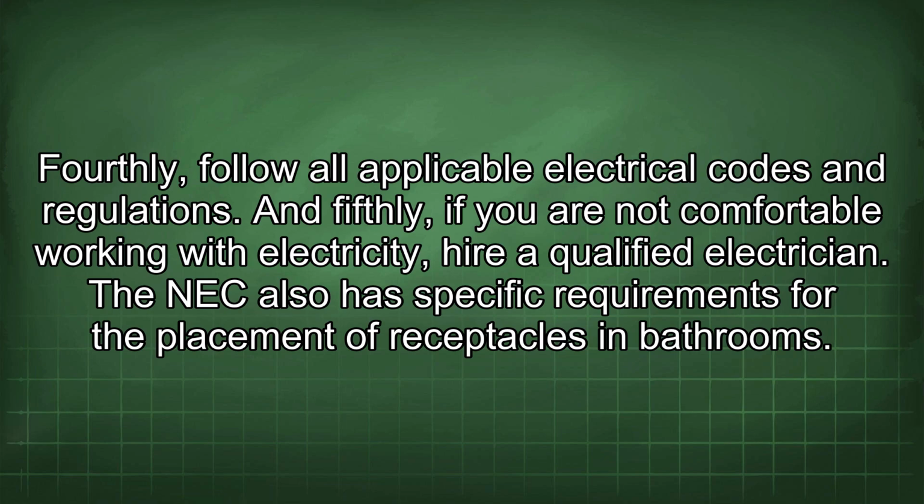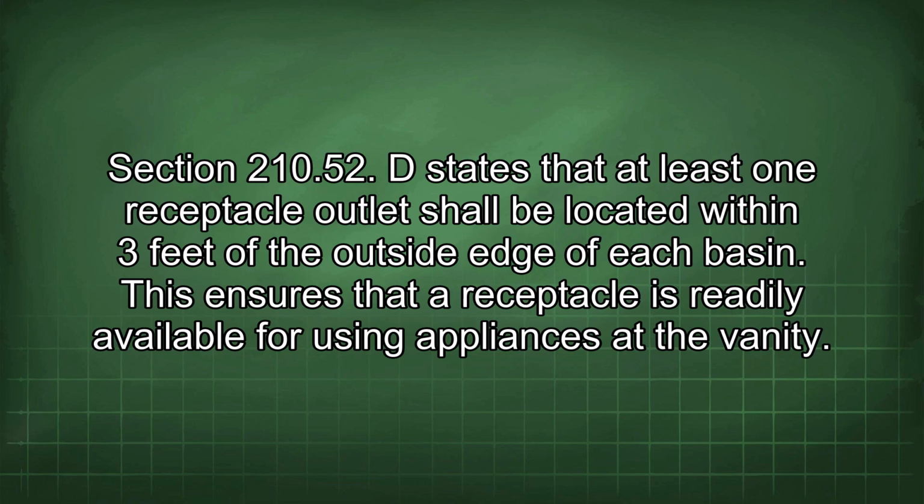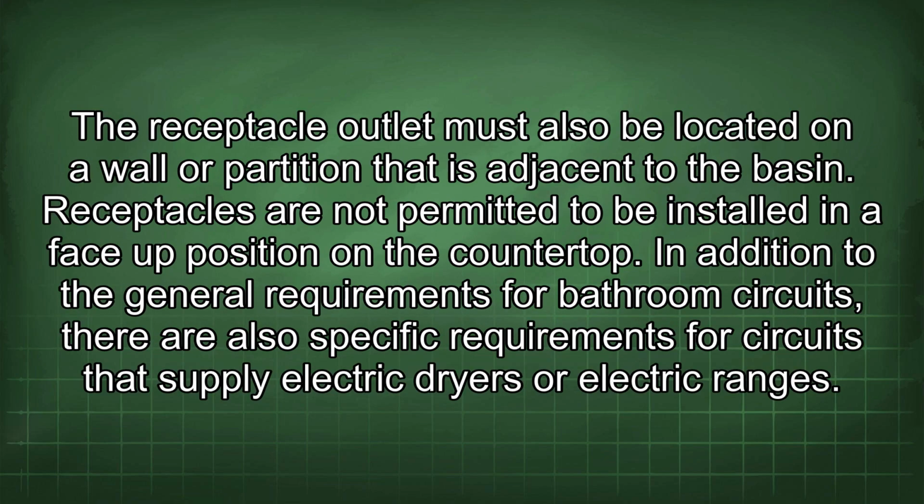The NEC also has specific requirements for the placement of receptacles in bathrooms. Section 210.52 D states that at least one receptacle outlet shall be located within 3 feet of the outside edge of each basin. This ensures that a receptacle is readily available for using appliances at the vanity. The receptacle outlet must also be located on a wall or partition that is adjacent to the basin. Receptacles are not permitted to be installed in a face-up position on the countertop.